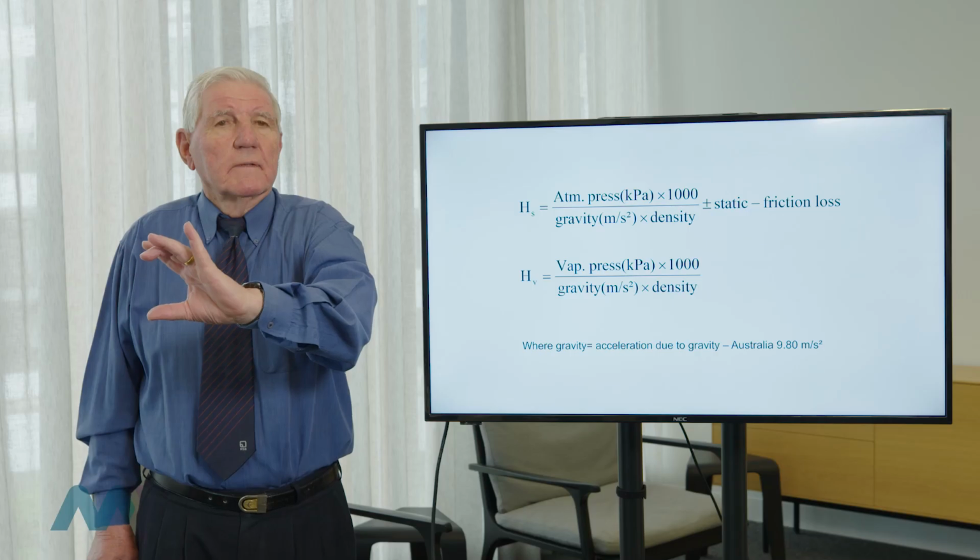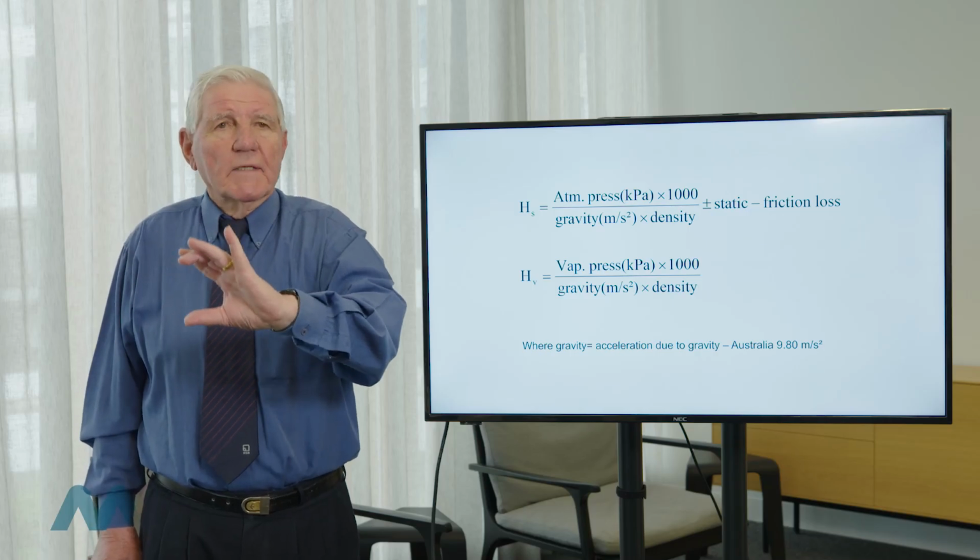The longer your pipelines are, the worse it gets. The more bends you have, the worse it gets. If you've got air entrainment, the worse it gets. All of these are negatives. And that will be reflected at the pressure that you read at the suction flange. But just because it's below atmospheric doesn't mean to say there's something wrong. It can be below atmospheric and still be okay.